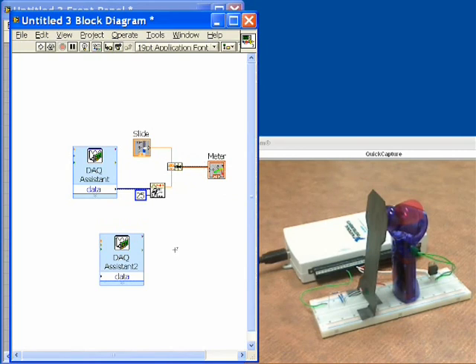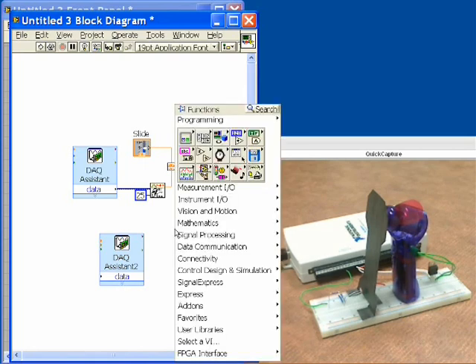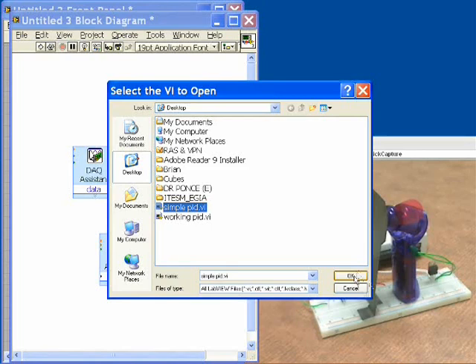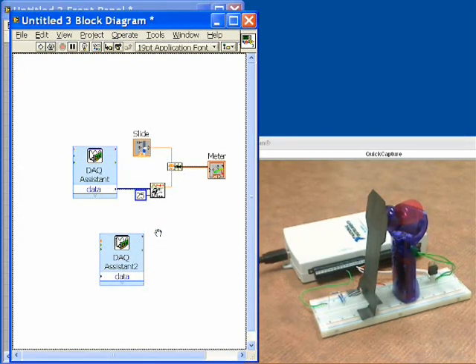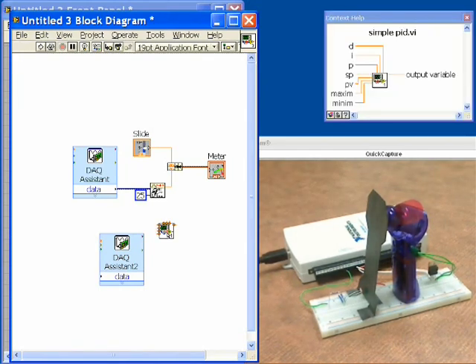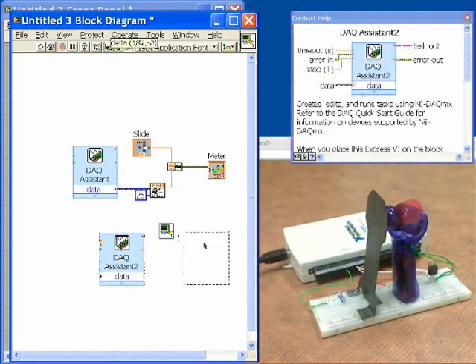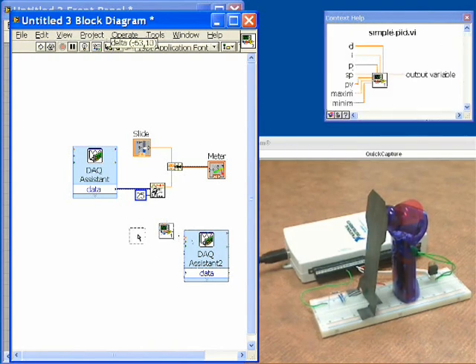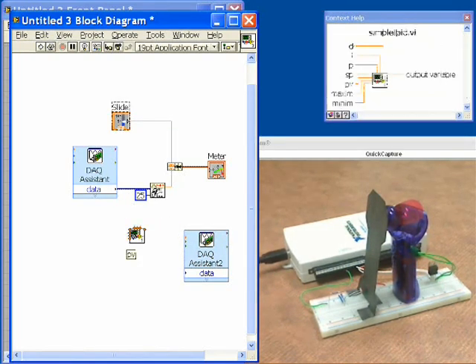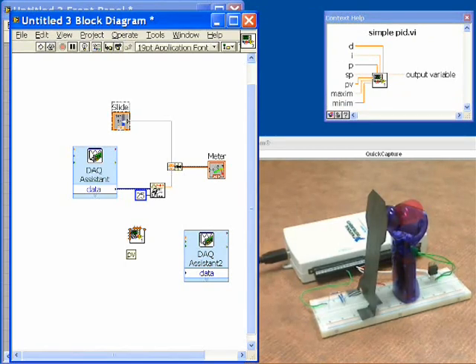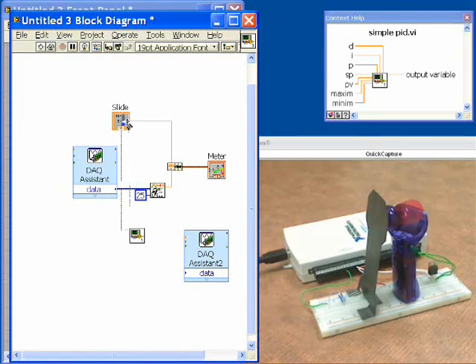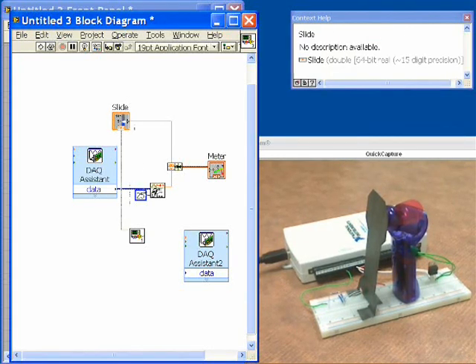So the next thing that we have to do is put the control algorithm in between this. And that control algorithm is called PID. We'll go and select it. And we're going to get a user created PID routine that we have because it's pretty straightforward. Now if we bring up the help window, you can see how we wire this up. The way that we wire this up is we're going to take the set point which is our slider. You can remember that that was from our front panel. And we're going to wire that into this PID control so that it will be an input into our PID. And that wires up to something called SP. And we'll click on that and we'll come up to our slider and we'll connect it in. So that's fine.